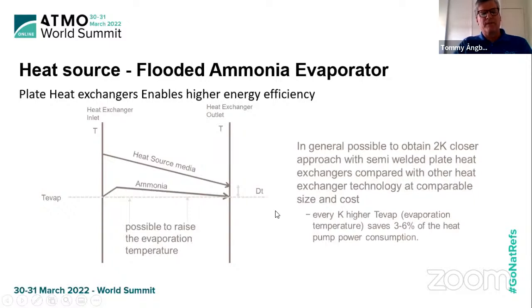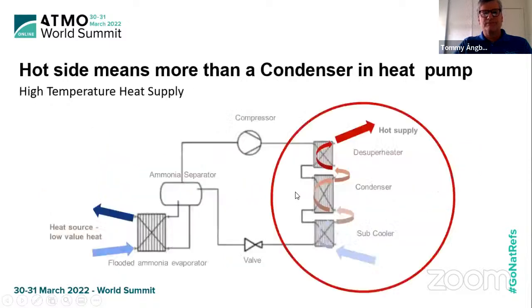That was the cold side. Try to take out the most heat from the source you have at the highest possible evaporation temperature. That will increase efficiency. On the hot side, we also want to extract as much heat as possible, and that's typically done by not only using the condenser function, but also cooling the hot gas from the compressor in the desuperheater, where you cool the gas from the highest temperature down to where condensing starts, and then condensing, where most of the energy is transferred, and then the subcooler. The subcooler is also free energy that you can use to increase your overall efficiency.